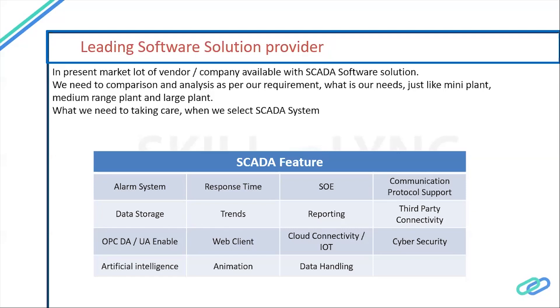For alarm systems configured as per equipment safety: for example, if a vibration sensor is on a rotating device like a cement mill, and the manufacturer specifies a maximum vibration of 5mm, then in the alarm system you define: 3mm as alarm, 4mm as alarm high, and 5mm as alarm high-high with a trip. This is how alarm response is configured in SCADA.